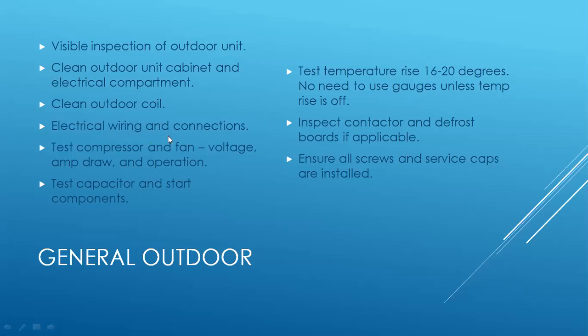There again, check your electrical wiring and connections. Look at your wiring, look at your terminations. Do you see any bubbled up wiring? If anything like that's there, make notes of that. If you need to make any corrections or terminations, correct that. Note that on your invoice. Point that out to the customer. Whether or not you charge depends on the company. But if you don't charge, let them know what you did. That's a good service to the customer.